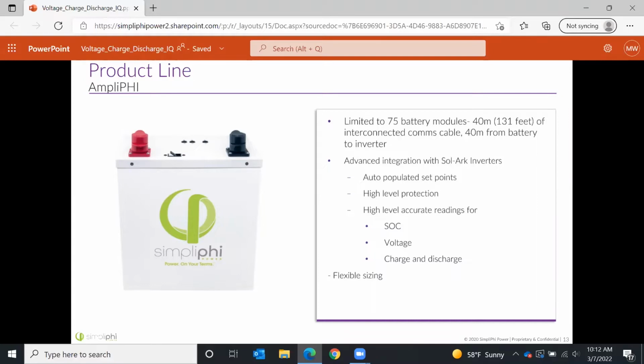You can connect up to 75 battery modules in parallel. So notice here there is a limitation on the scalability of the system because the battery communications lines have a max distance over which they can accurately receive communications. This is not the case with Phi batteries. So with our standard products, you can actually scale as many as you want in parallel. I've seen systems of over 100 Phi 3.8 kilowatt hour batteries. So we're talking over 400 kilowatt hours. Meanwhile, it's really rare to see a system of that size. I think most of you here on this webinar, seeing your names, I don't think you're going to run into that issue anytime soon. Hey, I hope you do. I really hope you do. But the 75 battery limit is a pretty rare limit to bump up against.